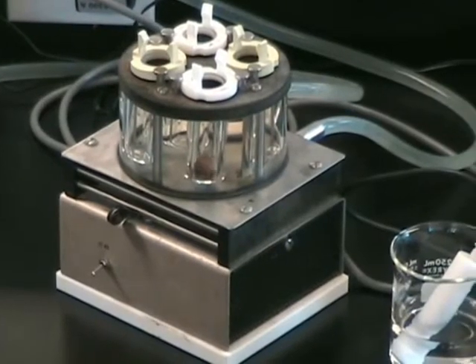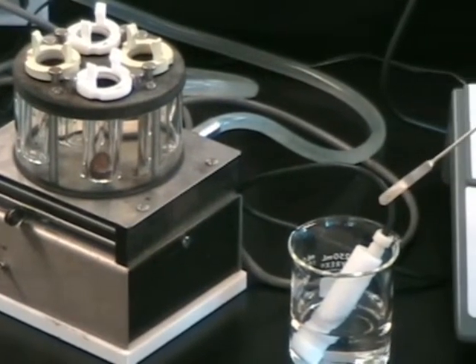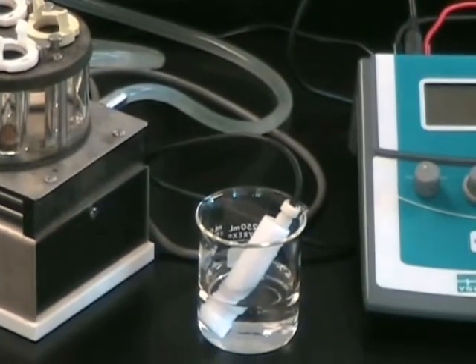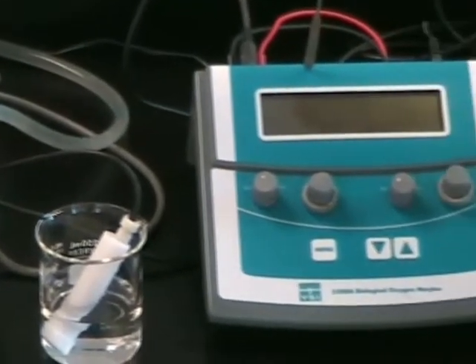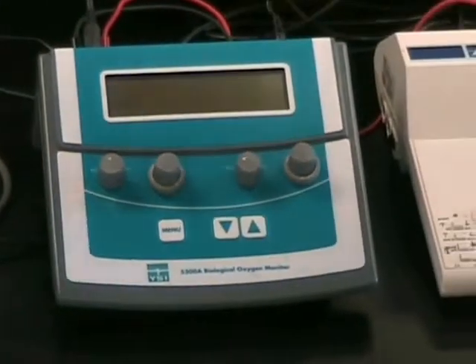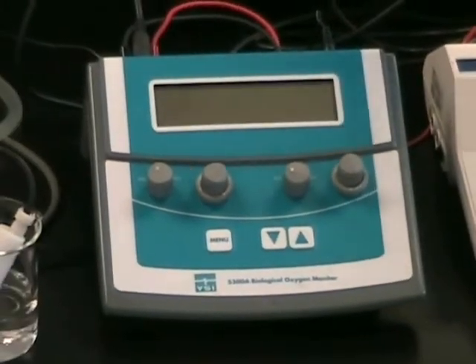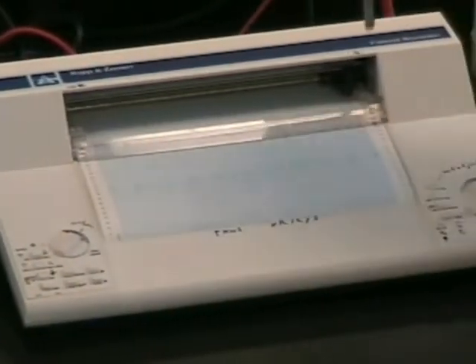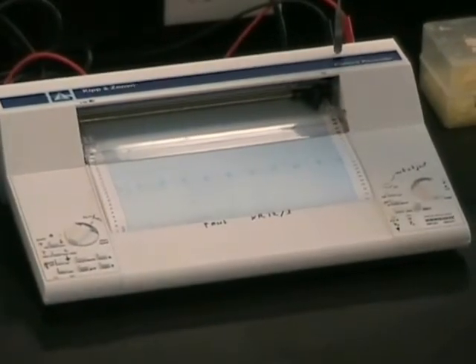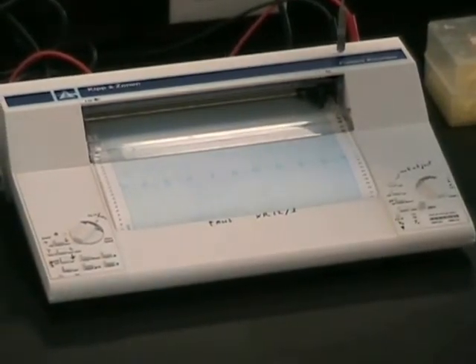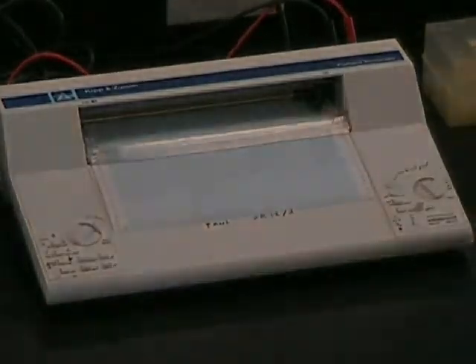Over here we have the electrode itself to measure the oxygen, and this unit is the amplifier. So eventually the electrode picks up a micro signal, sends it to the amplifier, gets amplified, and then the data will get shipped to the recorder over here. So on this recorder we'll pick up the signal.